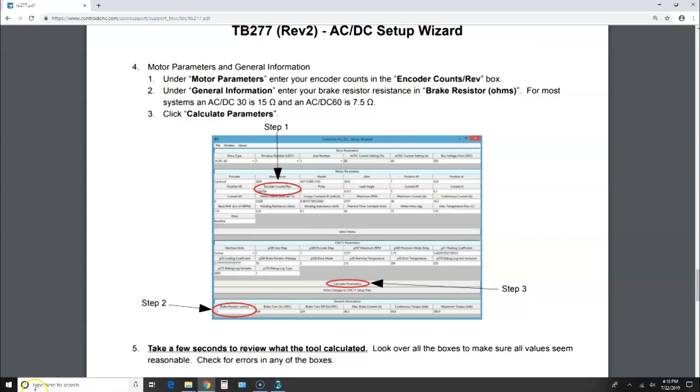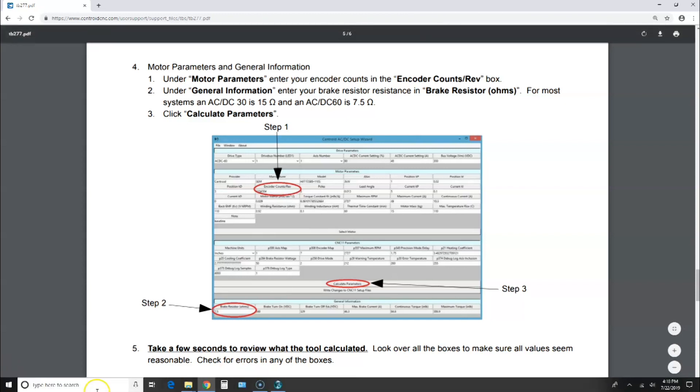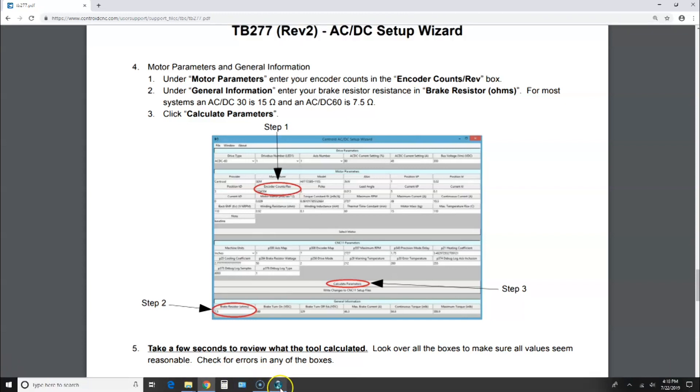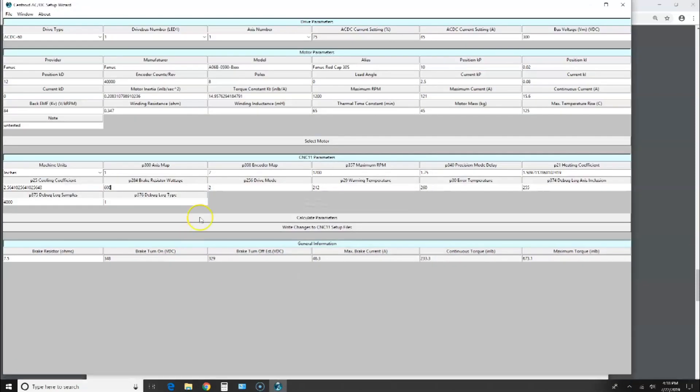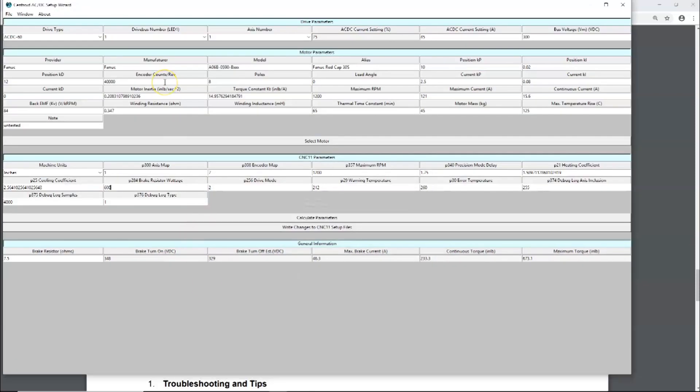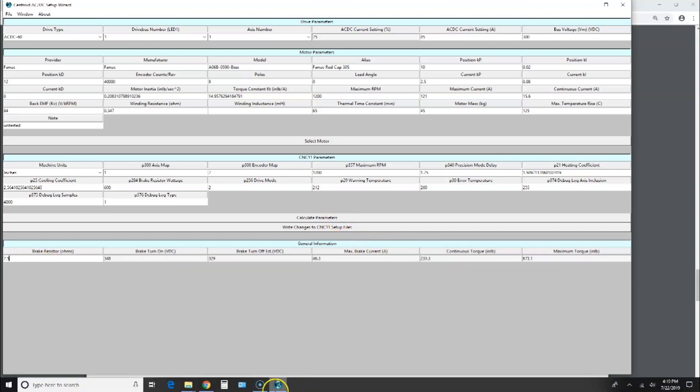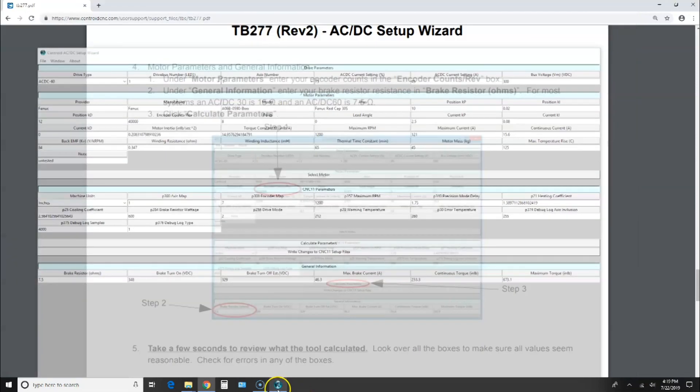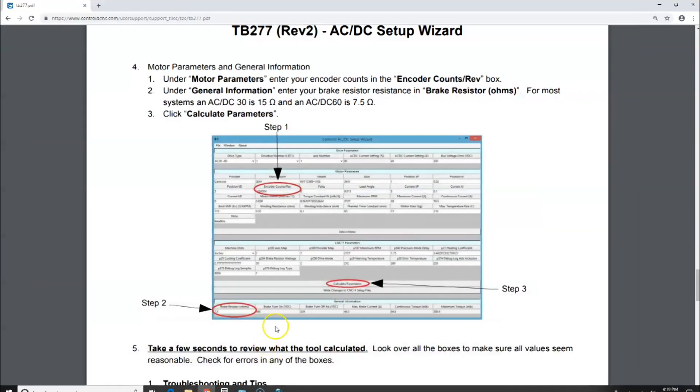Let's go to the encoder box. In my case, I am using a 40,000 count encoder. It's a native 10,000 line, and quadrature is 40,000, so we've got that correct. Then down here under braking resistor, we are using seven and a half ohms. Then it says to, I believe the next step was to calculate parameters.